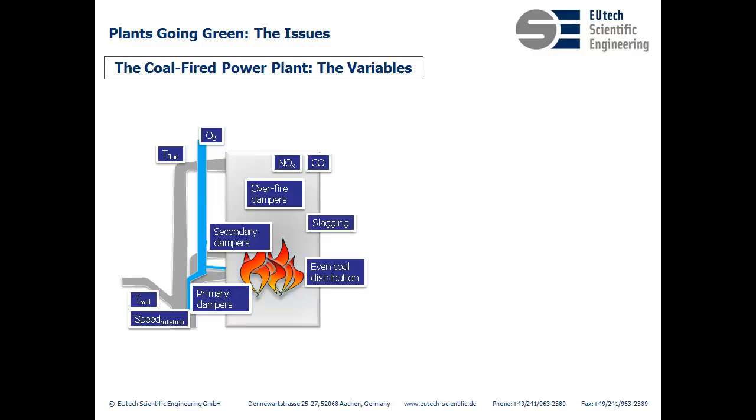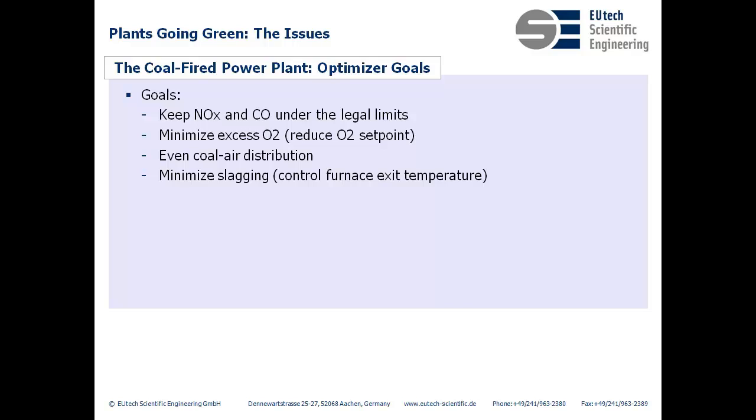That said, I'm going to go over the goals now we have for such an optimizer. Foremost, the optimizer has to ensure that both NOx and CO remain under the legal limit. With that constraint, it then aims to minimize the amount of oxygen needed to improve the efficiency.